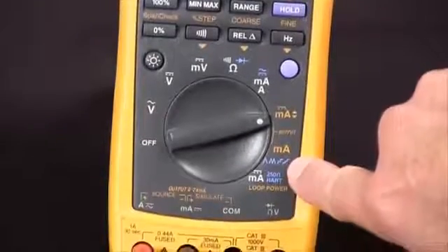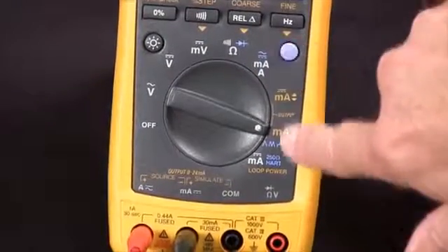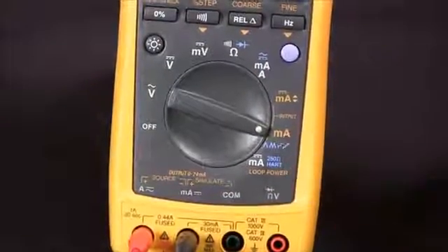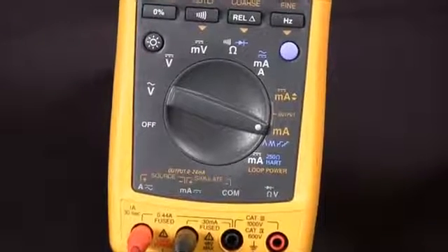With the blue key we can select one of those four, and that's how we source 4 to 20 milliamps DC with our 789 process meter.